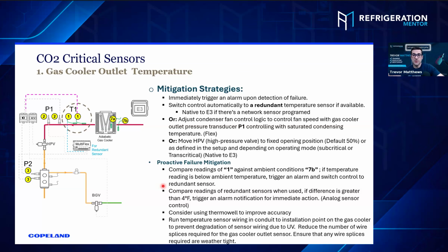So those are things you can do. If you have to start putting like a 5 or 6 or 8 degree offset in, that sensor needs to be replaced. There's no just putting offsets in, especially these sensors. Now, if it's a case controller, okay, throw a little offset in there, but not on these sensors here. You just pull a new one.